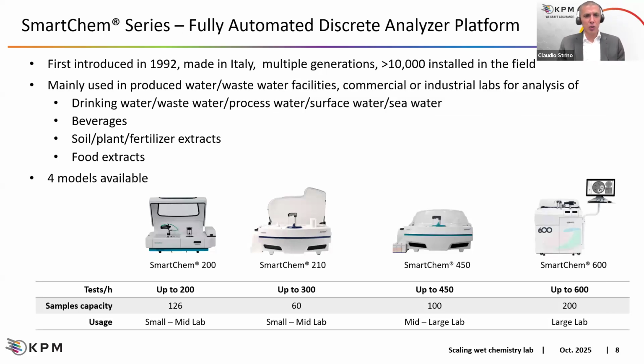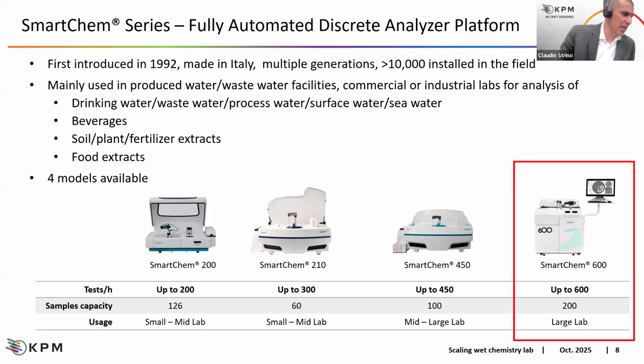The first unit was introduced in the market in 1992, made in Italy. So the factory is based in Italy. And we have more than 10,000 units installed in the field. Those units are mainly involved in water and wastewater facilities, for commercial or industrial labs analyzing water, beverages, as we saw, soils, plant fertilizer, and food extracts. We have 4 models available: SmartChem 200, 210, 450, and 600. And the one that can really fit the needs of high throughput labs is the SmartChem 600, because as we can see here, we have the possibility to load on board up to 200 samples in one shot.